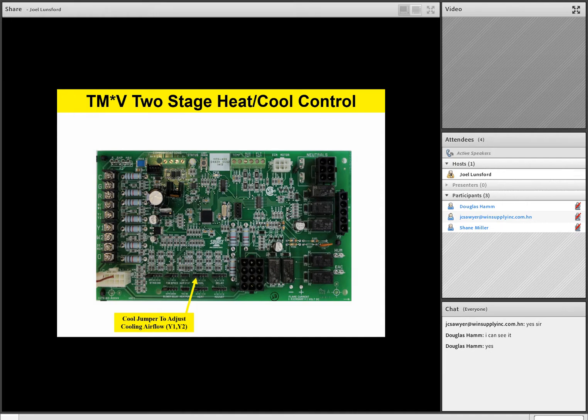Right below your cooling bank of jumpers is a heating jumper. The heat jumper adjusts your heating airflow. So if I have a W1 or a W2 call from the thermostat for first or second stage heating, it'll look at this jumper selection to know where it should be for heating airflow. From the factory, we typically set up the heating airflow on the furnace, because based on the size of the furnace we already know what the heating airflow should be, so that normally doesn't need to be adjusted. But remember, based on the outdoor unit, the technician will have to set up the cool and adjust jumpers we just talked about.